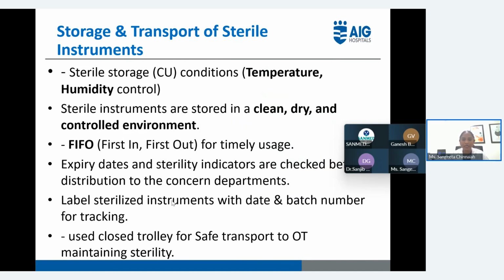For whatever items we are keeping in sterile storage, we first need to check the expiry date. We need to use them before the date only. Otherwise, if we didn't use them, we need to send them again to the CSSD for re-sterilization. The expiry dates and sterility indicators are checked before distribution to the concerned departments. Yes, the biological indicator results: only after the results are we distributing the sets to the concerned departments.